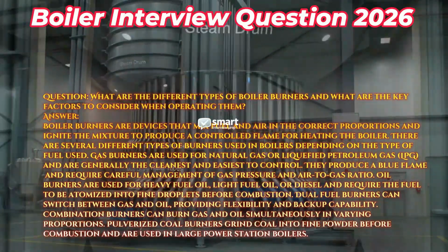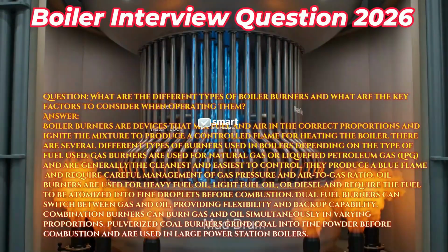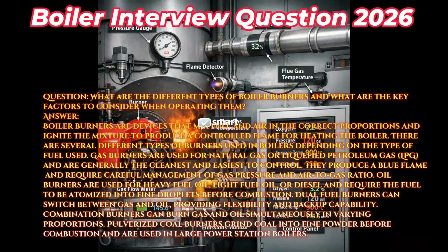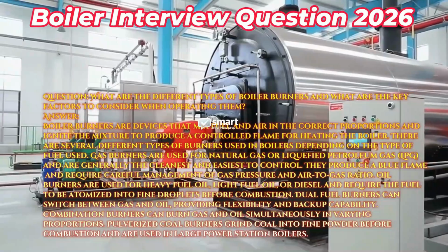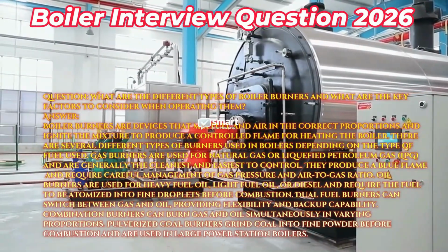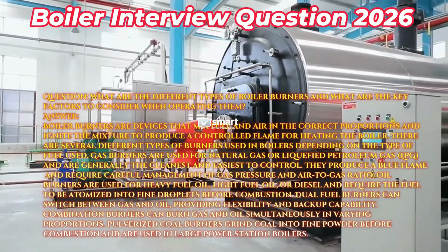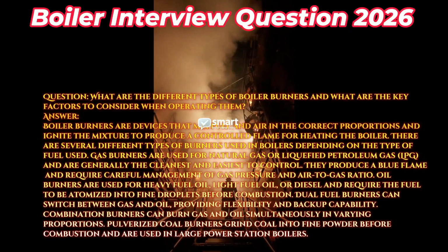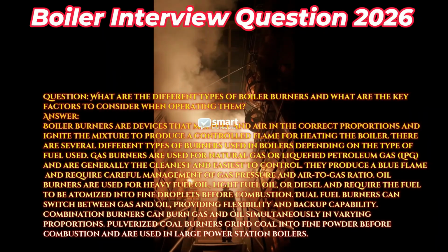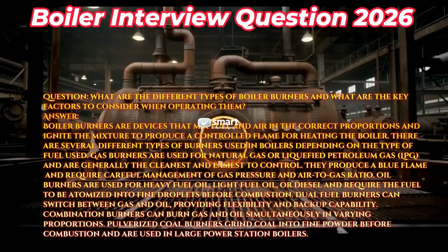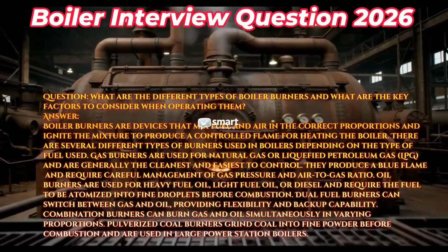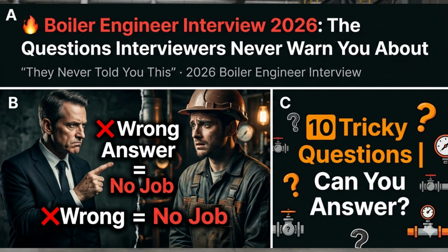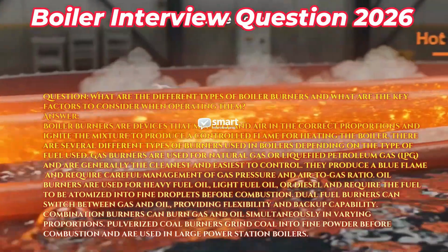to produce a controlled flame for heating the boiler. There are several different types of burners used in boilers depending on the type of fuel used. Gas burners are used for natural gas or liquefied petroleum gas, LPG, and are generally the cleanest and easiest to control. They produce a blue flame and require careful management of gas pressure and air-to-gas ratio. Oil burners are used for heavy fuel oil, light fuel oil, or diesel and require the fuel to be atomized into fine droplets before combustion.